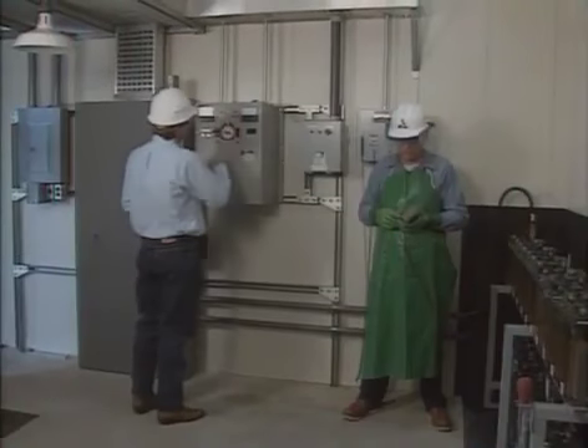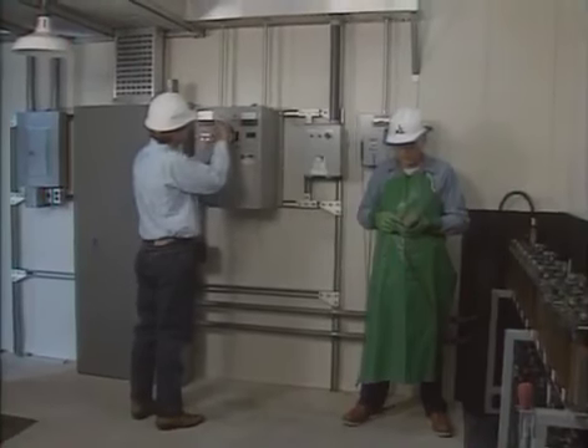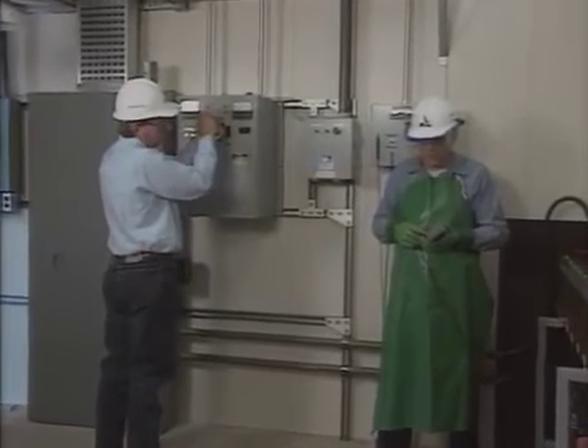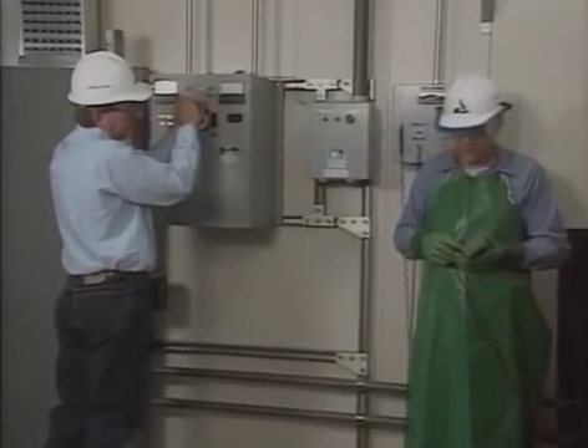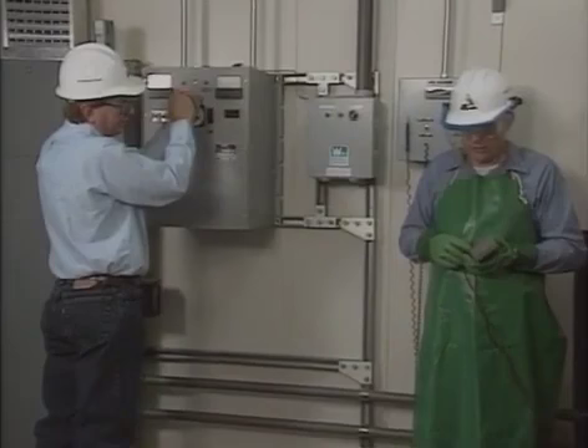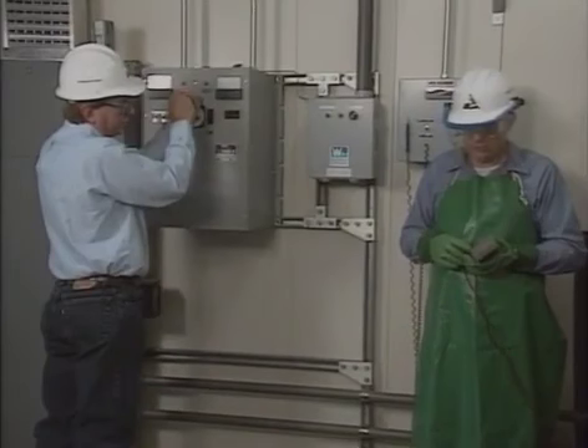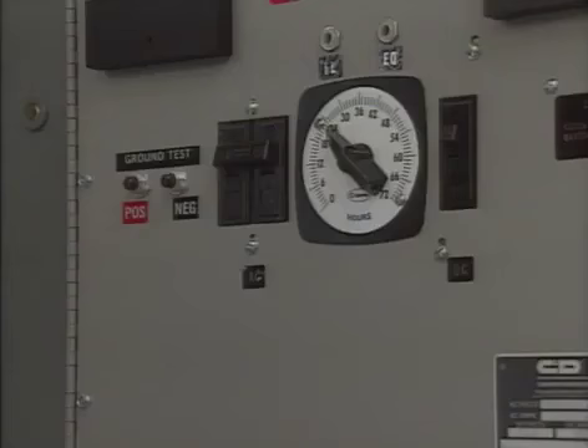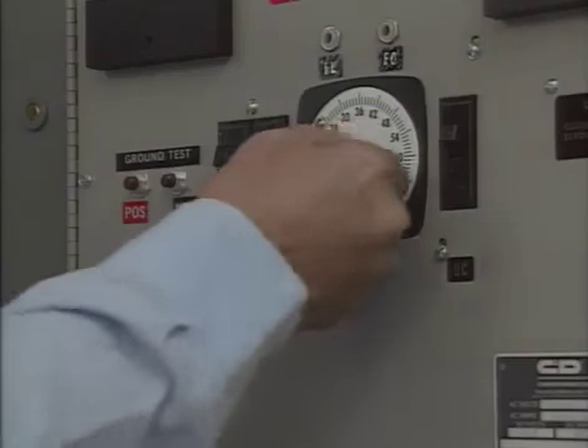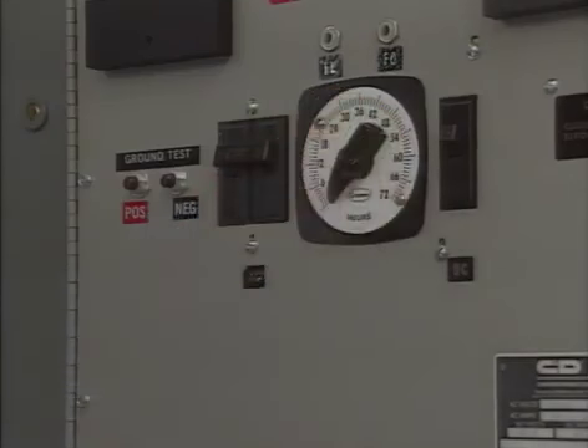The voltage is also checked with the charger in the equalizing charge mode. Again, if necessary, the equalizing voltage potentiometer is adjusted to provide the required equalizing voltage output to the battery. After the equalizing voltage output is checked, the float equalize switch is returned to the float charge mode.